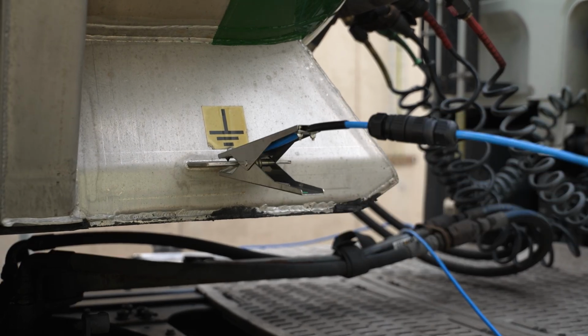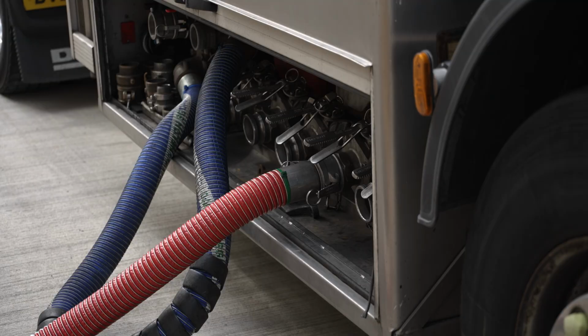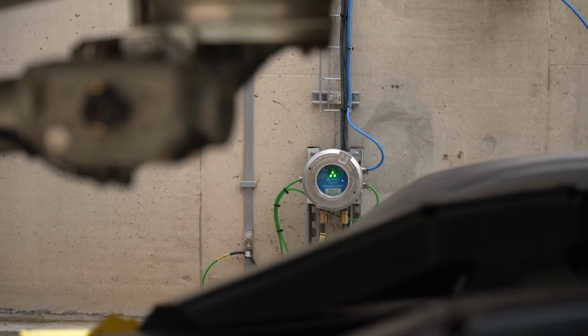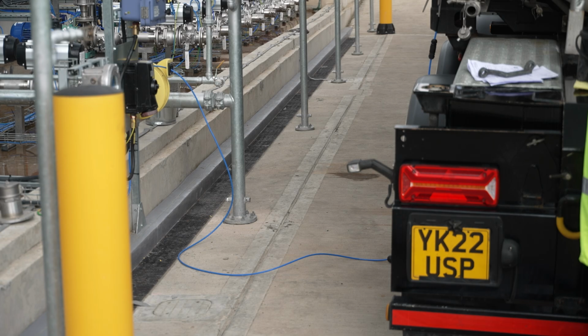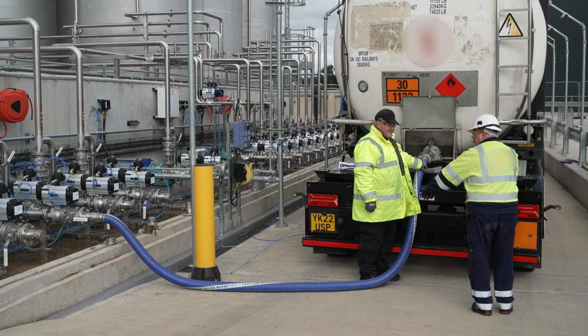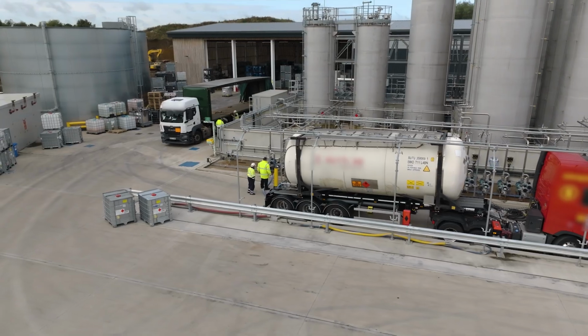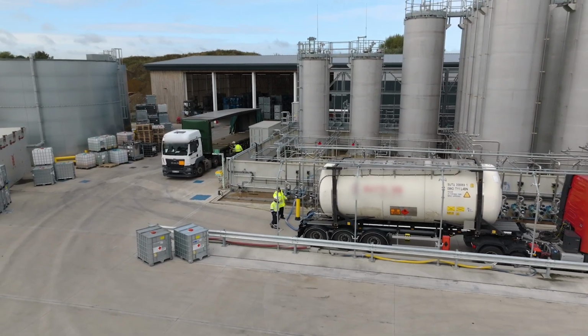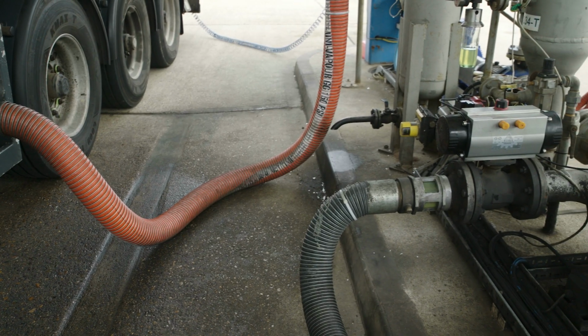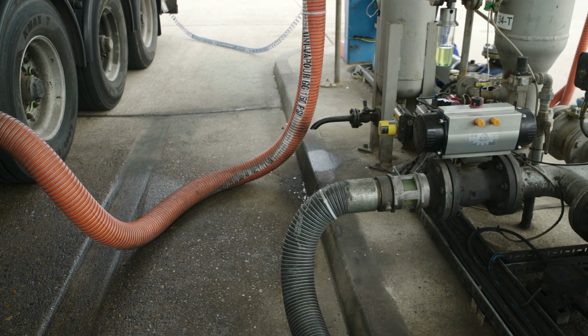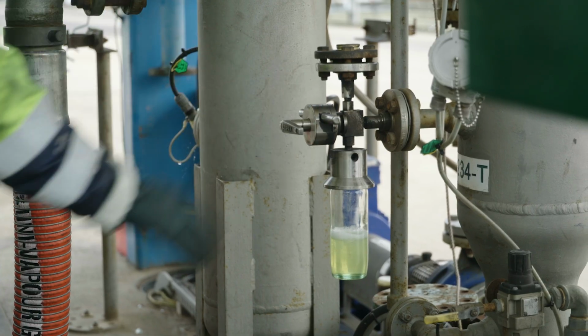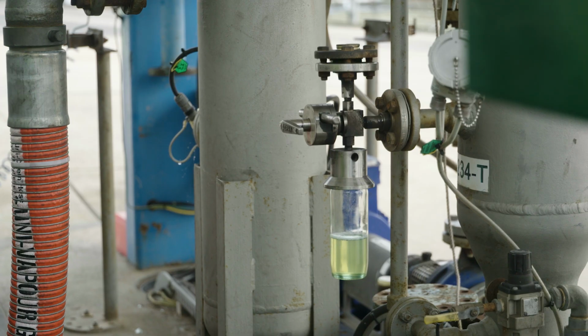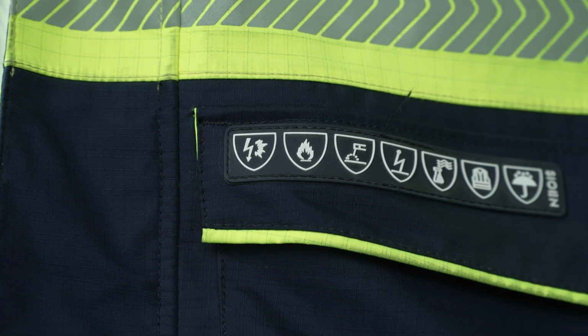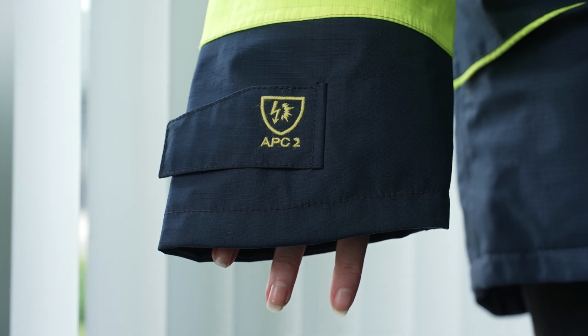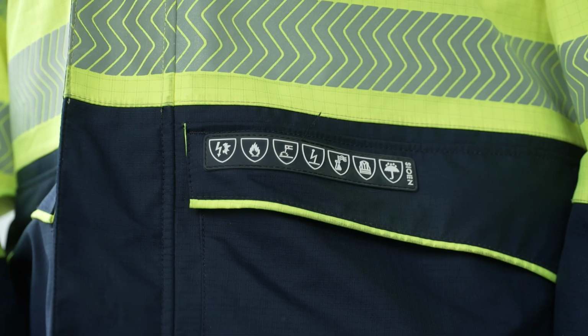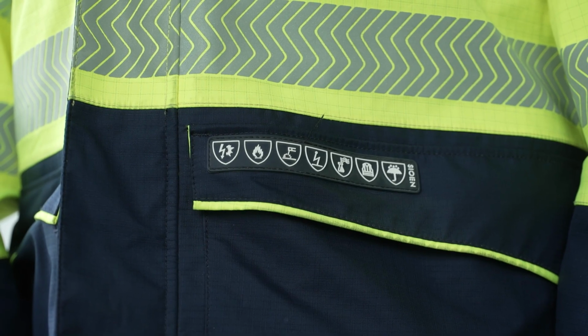When filling or unloading road tankers, the connection to earth should not exceed 10 ohms. In all instances, the earthing clamp must be attached to the vehicle before any operation commences and should not be removed until all operations are complete and there is no presence of vapor. Sampling equipment should be of conductive material and bonded to the tank. Sampling should only take place after the appropriate relaxation time has elapsed. If flammable liquids are handled, static dissipative personal protective equipment, particularly footwear, should be worn and tested on a regular basis by all people present.